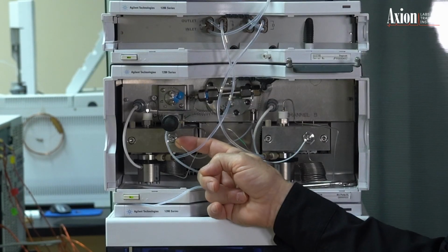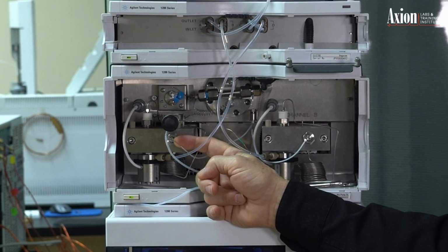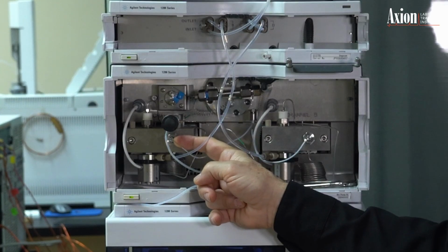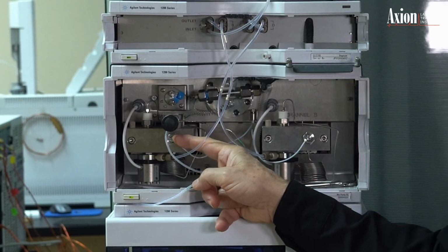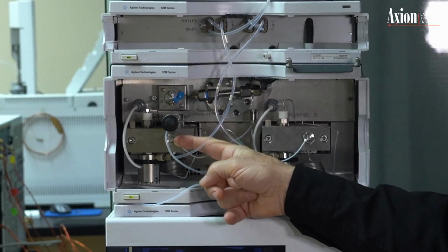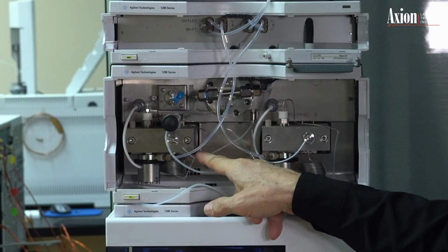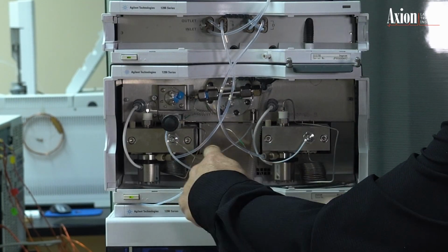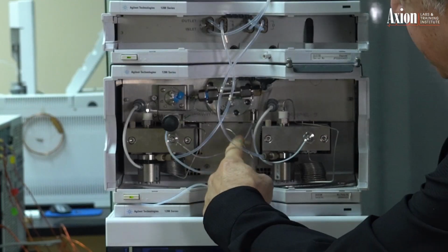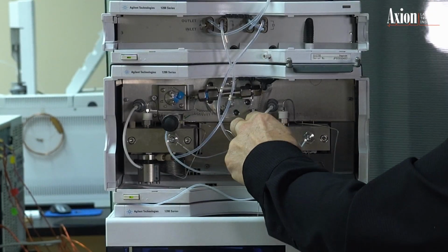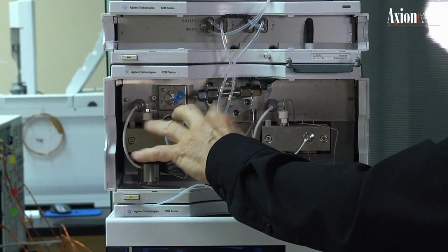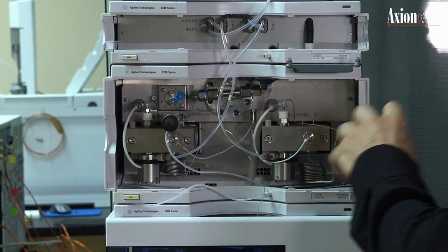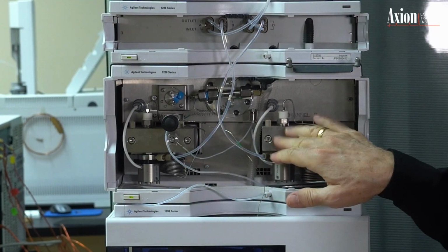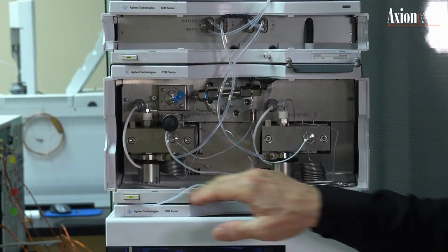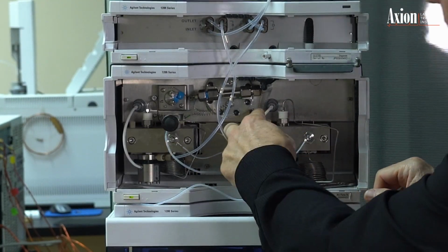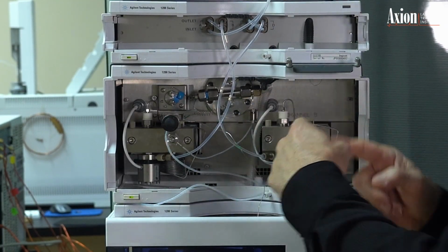Now, if this were a quaternary pump, we'd come right out of the pump with our blended mobile phase and go to the autosampler. But at this point, remember, it's not blended. This is just the pure 100% A. So we're coming off here. Now, it takes a little bit of an extra path because remember, we now have to blend it with what's coming out of B. Whatever I said about pump A, the exact same thing is happening in pump B. 2 reciprocating pistons. These guys are pumping methanol. These guys are pumping water. The 2 come together in this T. So 2 come in, 1 comes out.